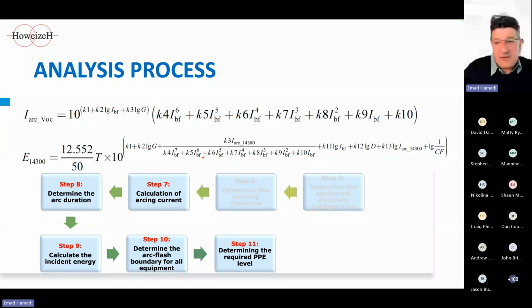This is just one example of that equation. Or the arc duration, which is the critical factor in determining the severity of the arc flash incident. It's defined as the time it takes for the upstream energized source to stop providing current to the arc fault, which depends on the protection devices and the time for the circuit breaker to open, or the time for the signal traveling, any intermediate relay or lockout, and also the time it takes for the stored energy to be discharged through the arc flash. So this is the clearing time, actually, or defined as the clearing time.